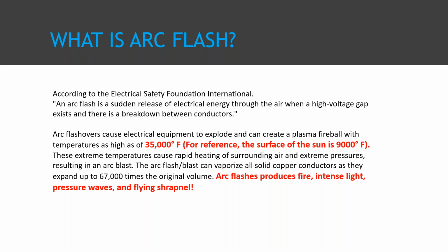That arc flash produces fire, intense light, pressure waves, and flying shrapnel. So even if you're completely outfitted with the proper PPE, if you're exposed to an arc flash, if the burn doesn't get you, perhaps the shrapnel does. If the shrapnel doesn't get you, perhaps getting thrown across the room by the extreme pressure will. So we don't want to be involved in an arc flash. And if there's anything we can do using technology to mitigate the possibility of being involved in an arc flash, we want to try to do that.